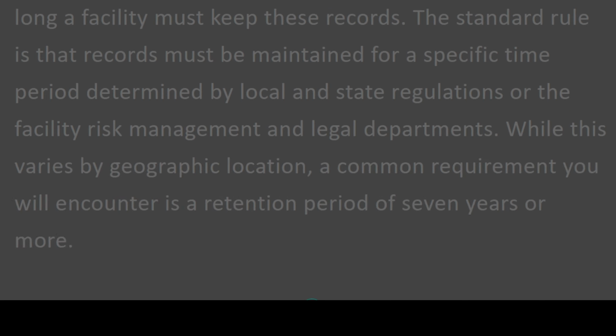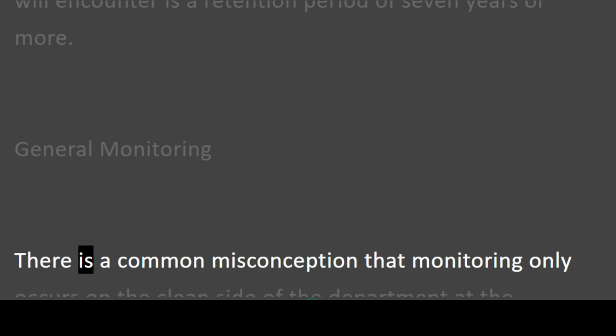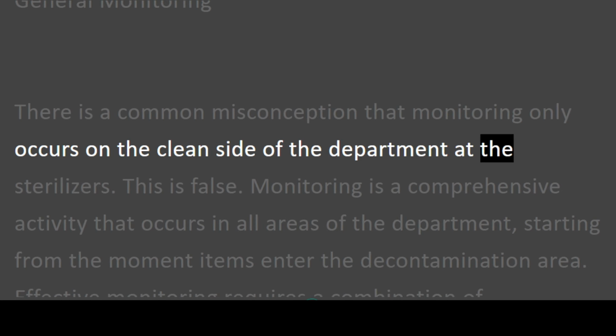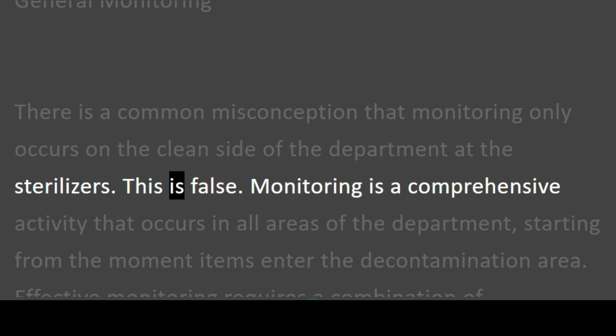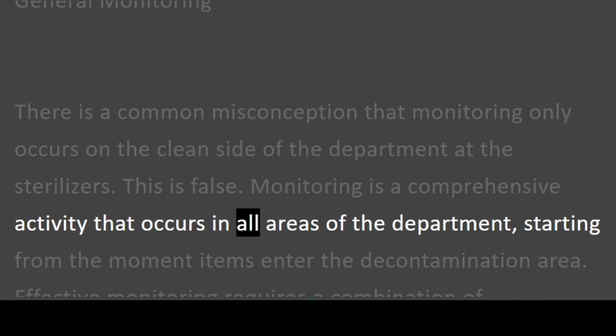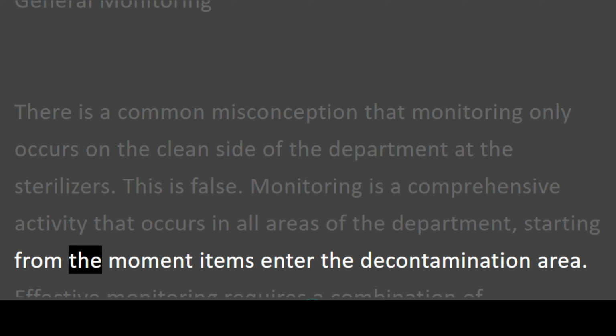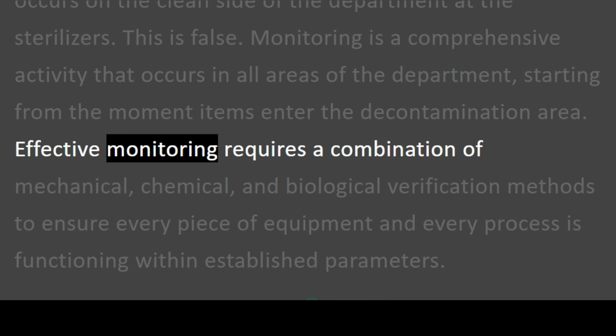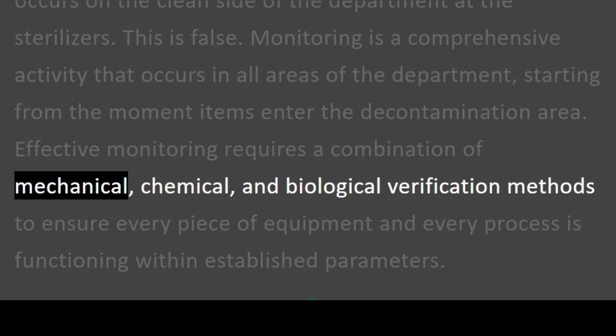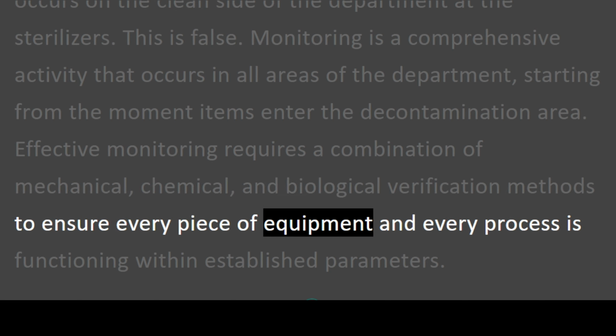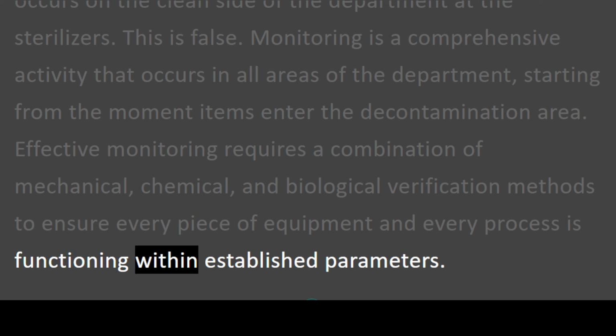General monitoring. There is a common misconception that monitoring only occurs on the clean side of the department at the sterilizers. This is false. Monitoring is a comprehensive activity that occurs in all areas of the department, starting from the moment items enter the decontamination area. Effective monitoring requires a combination of mechanical, chemical, and biological verification methods to ensure every piece of equipment and every process is functioning within established parameters.